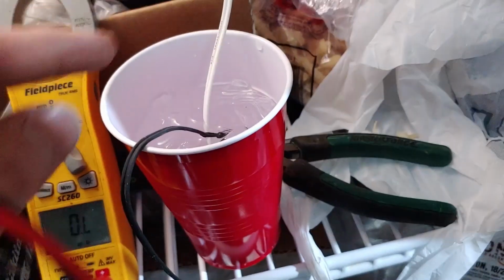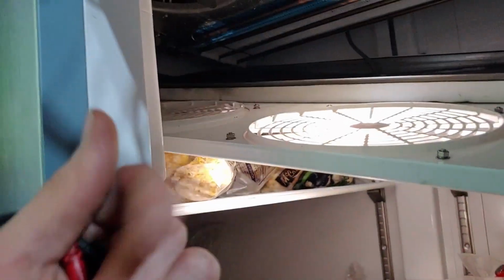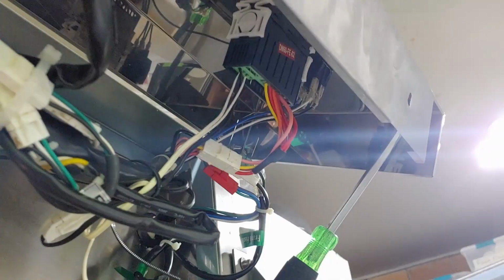So real quick, I want to show you how to test the probes on an Arctic Air freezer. Most freezers and coolers that use these little Dixell controls are going to have these 20,000 ohm sensors. You can see this one has two, one white, one black. In this particular one, the white one goes to the coil and the black one goes to the cabinet.